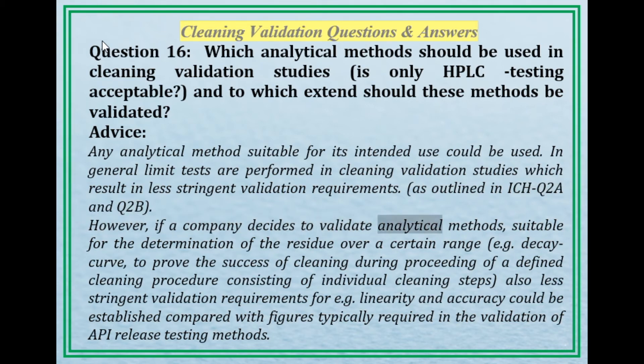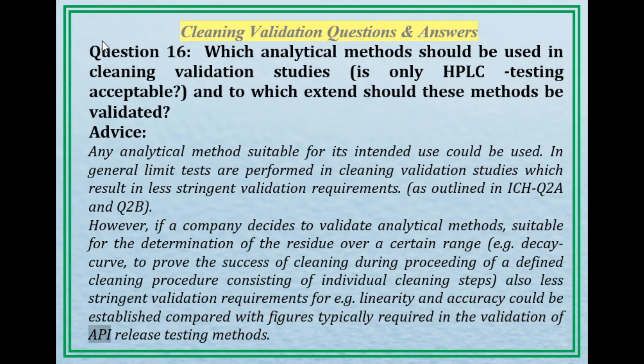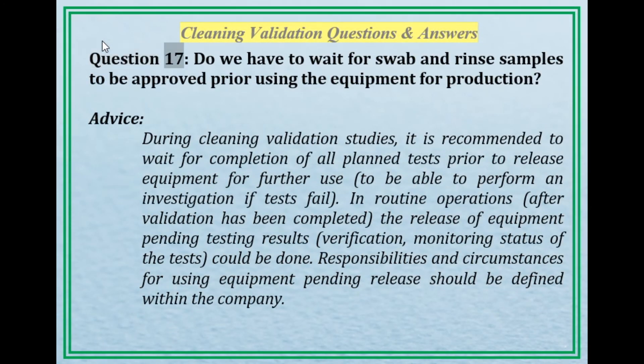However, if a company decides to validate analytical methods suitable for the determination of the residue over a certain range — for example, a decay curve to prove the success of cleaning during proceeding of a defined cleaning procedure consisting of individual cleaning steps — less stringent validation requirements for linearity and accuracy could be established, compared with figures typically required in the validation of API release testing methods.